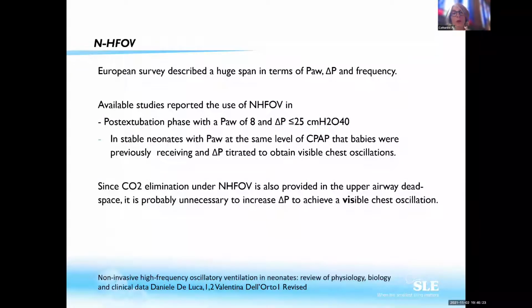What we see here is a European survey, where we looked at the settings that were used. In the post-extubation phase, they were setting a MAP which was around 8 most of the time, and they had a delta pressure most of the time which was at 25 cmH2O. So don't expect to see some vibration of the chest. Sometimes you might not see any vibration of the chest. It's fine with that. No worries about it.